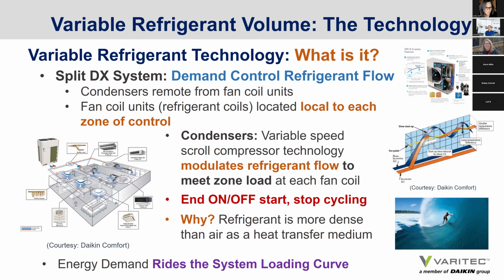So what is variable refrigerant volume? What is this technology, otherwise known by the popular acronym VRF? Well, instead of an all-air system that has a big air handler on the roof that pumps air throughout the building through large ductwork, and returns building air back to the air handler to be conditioned at the coil, we actually bring fan coils, distribute them throughout the building locally, potentially to each zone, or using ducted units to serve a discrete number of zones, and then actually move the sensible and latent heat energy at these fan coil units served by a condenser remote from that air handler. So you're actually bringing that refrigerant locally to each zone.